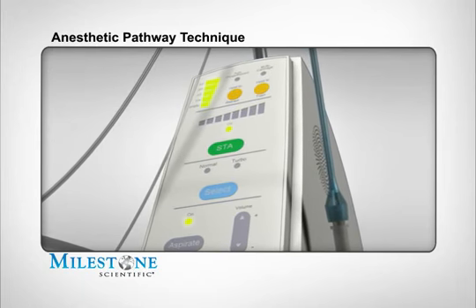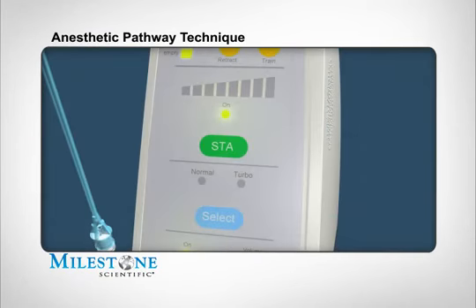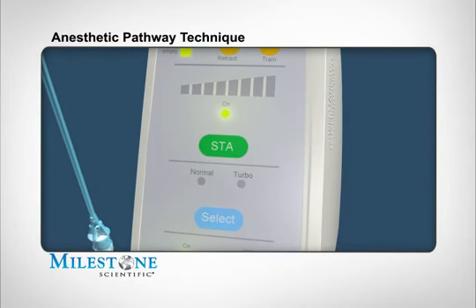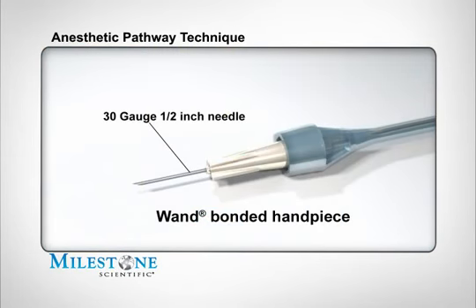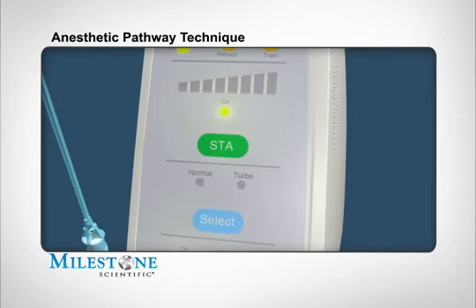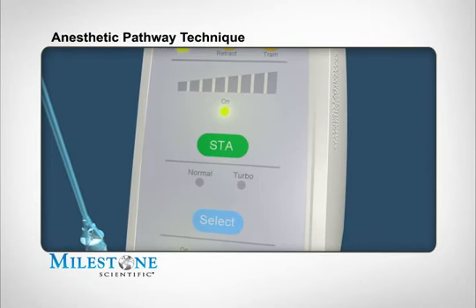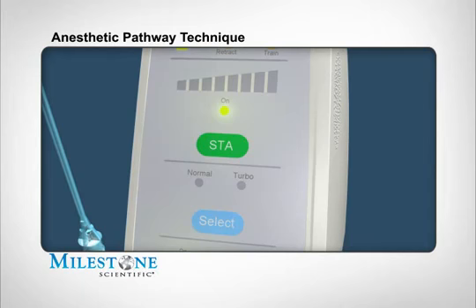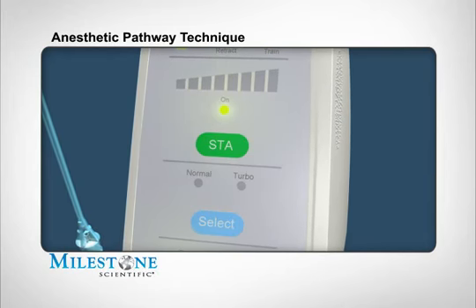Before you begin, verify the STA system is set to the STA mode. It's recommended that you use the 30-gauge, half-inch bonded STA wand handpiece when performing the Pre-Puncture Technique in the palate. It's critical to use the STA mode to ensure that a safe and controlled single flow rate is maintained throughout this injection. Delivering the anesthetic at a faster rate than the control flow rate can result in adverse tissue reactions and or tissue damage.